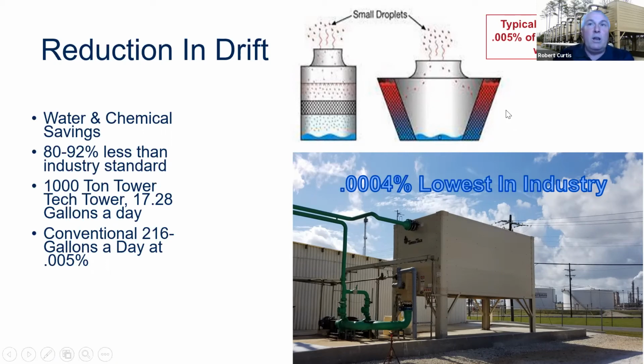TowerTech designed our tower so that drift is 0.0004%, which is 92% less than typical. That's due to our force draft design with a highly efficient drift eliminator, and our water distribution system's droplet size, part of our patented technology that achieves the lowest drift in the industry. On a 1,000-ton tower, you'd have 216 gallons of water leaving that cooling tower, exposing equipment or people to bacteria like Legionella. With TowerTech, you reduce that by 92%.